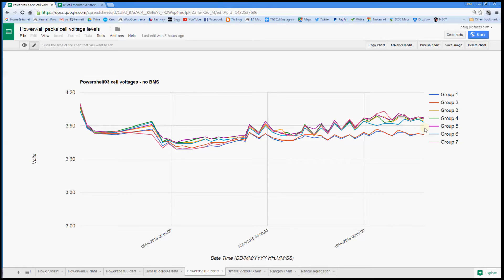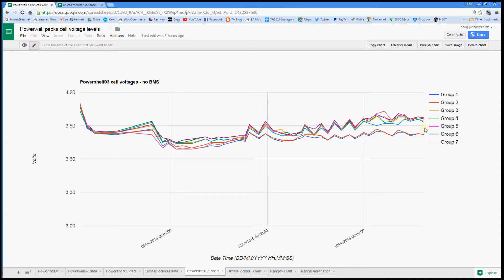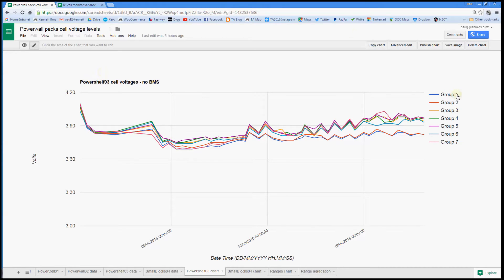But because this is the power shelf which uses battery holders, I can actually replace cells in these two underperforming groups live. I can just yank out the lowest capacity cell, slap in a higher capacity cell and hopefully bump these two lines back in with all the others. So that is what I'm going to do.